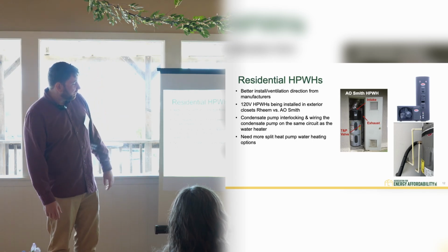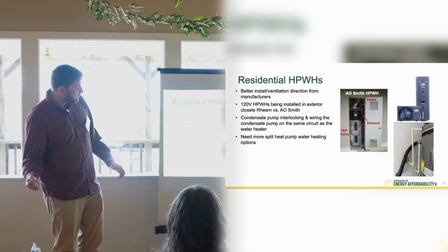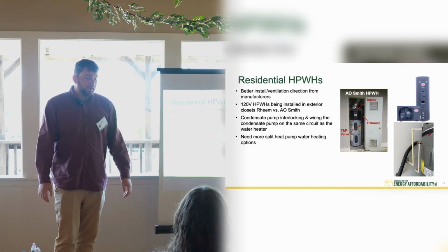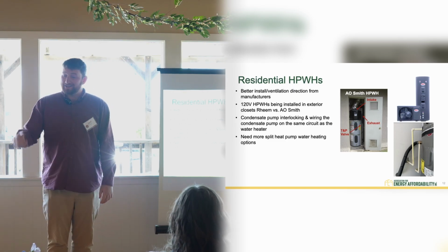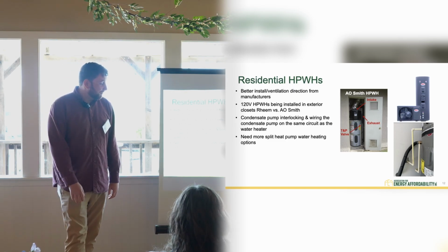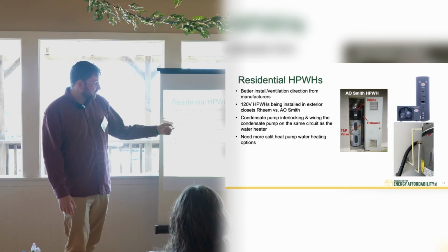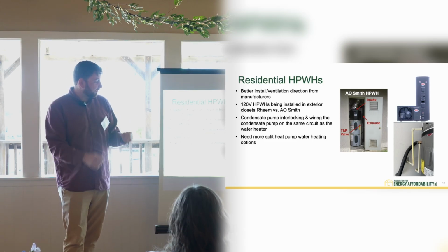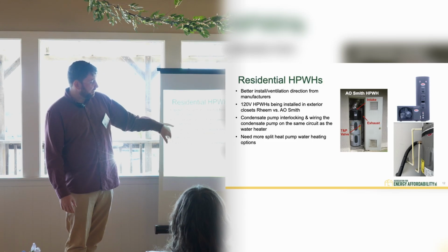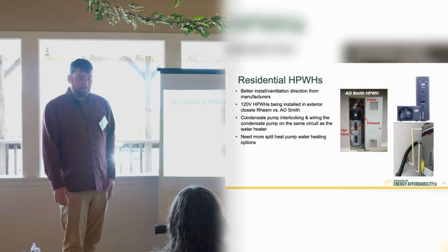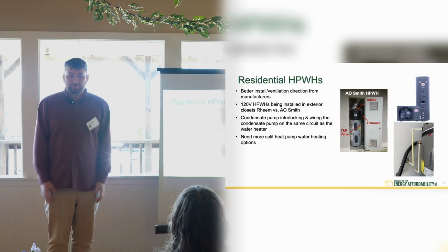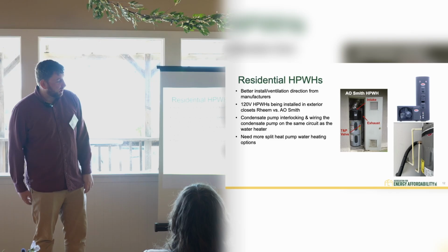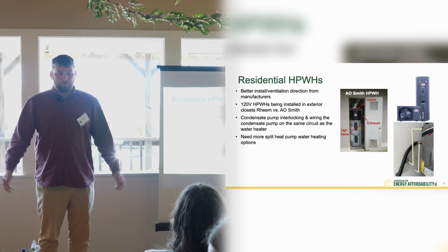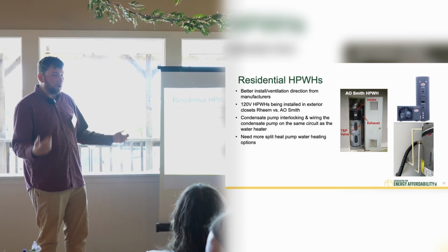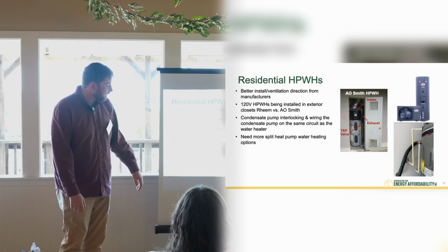This is a project that Andy and I are working on where we needed a condensate pump. Rheem doesn't have a way to interlock the condensate pump with their heat pump, which is required by code. So you're providing equipment that we can't meet code with, and it's just making it harder and harder to install this equipment.